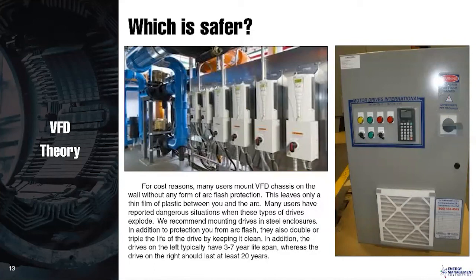But the drive on the left really has no protection. There's no place to put other components in there. And those drives on the left we find are lasting maybe 3 to 7 years. Whereas the drive on the right, if you keep it cool, you keep it clean, you keep it dry, you change the filters, you should easily get 20 years out of a drive like that.